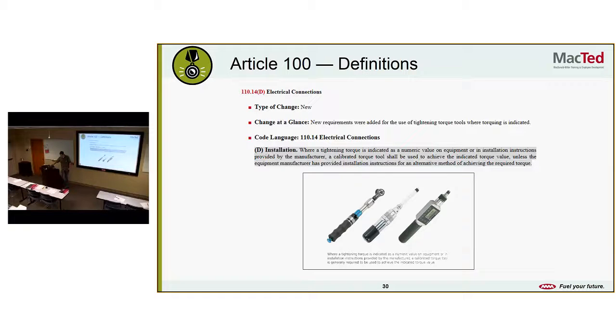We have a new definition for electrical connections. New requirements were added for the use of tightening torque tools, where torquing is indicated. So where a tightening torque is indicated as a numeric value on equipment or in installation instructions provided by the manufacturer, a calibrated torque tool shall be used to achieve the indicated torque value, unless the equipment manufacturer has provided installation instructions for an alternative method achieving the required torque. So, imagining some kind of a bus bar where you have to torque down bolts, now there's a requirement to actually use the tools that are called out for. I don't know how they enforce it, but at least now they're starting to address it, that you have to have these tools if you're doing that work. Our control panels have torque spec in it, so.